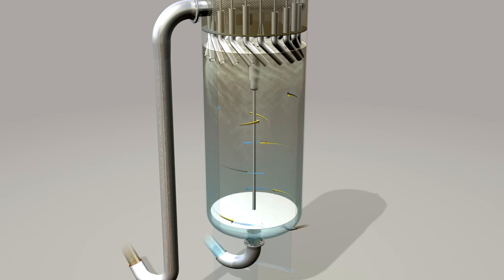Careful design using computational fluid analysis has led to a rotating toroidal flow path being created, which suppresses back mixing. The water passes through the lower chamber in what is known as a rotating plug flow, which leads to a higher oil removal efficiency than older designs on the market.